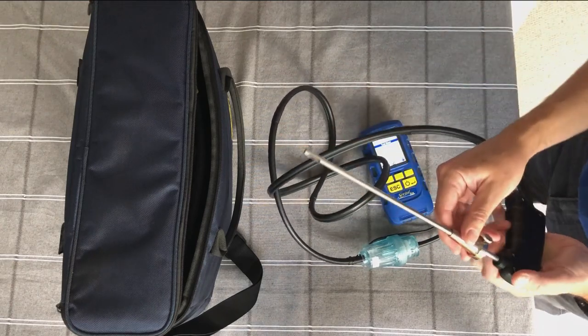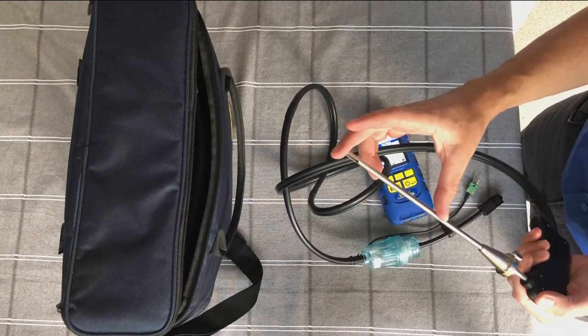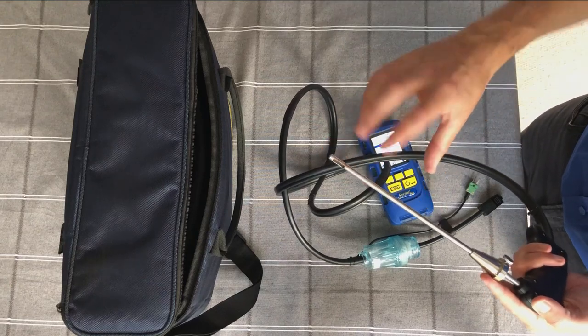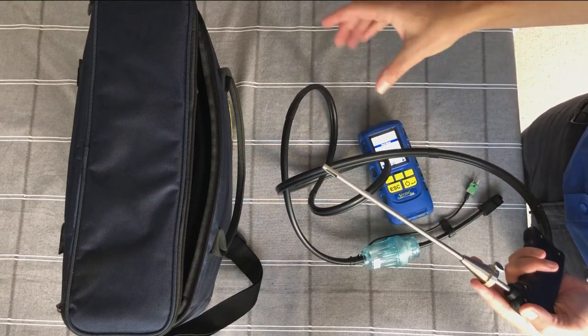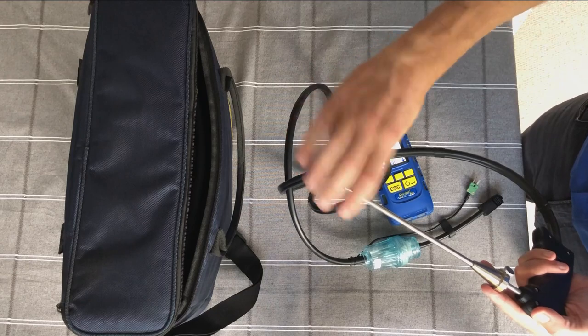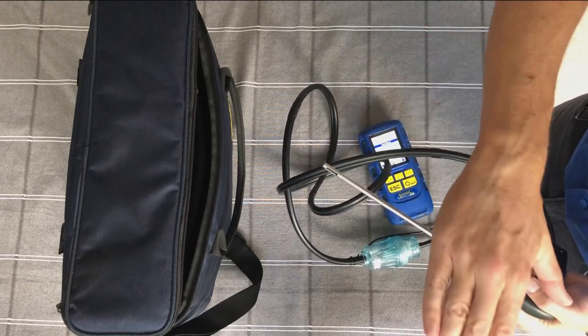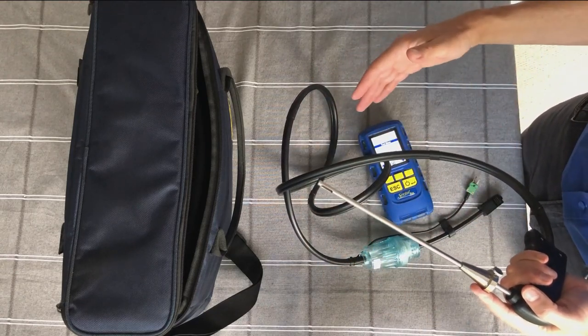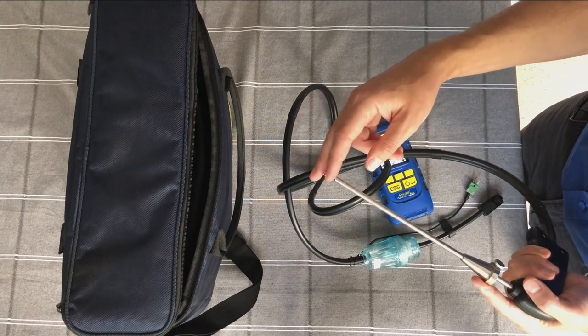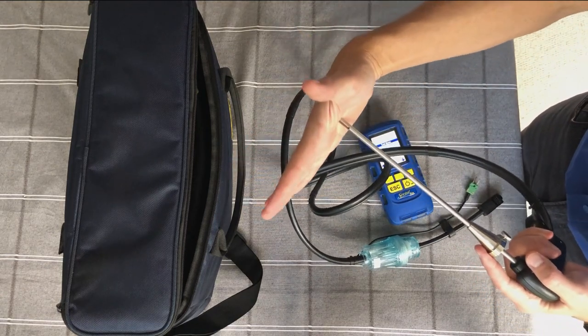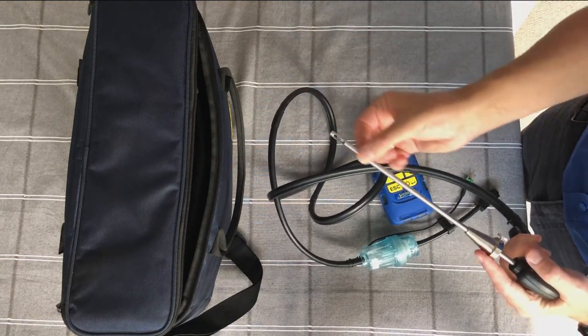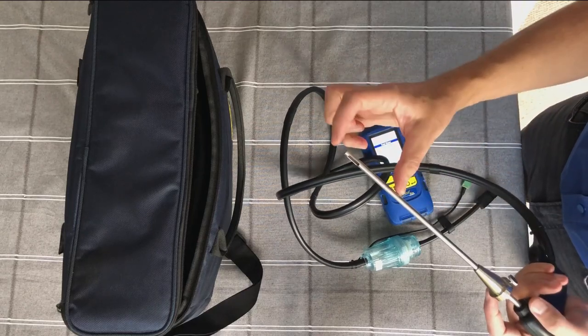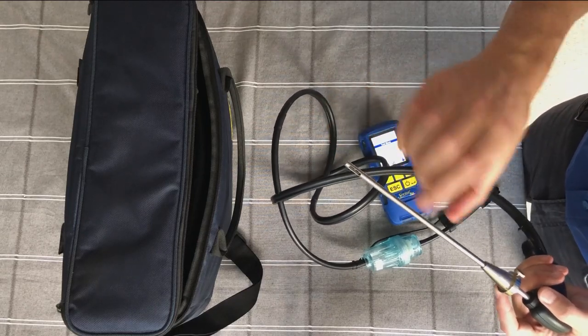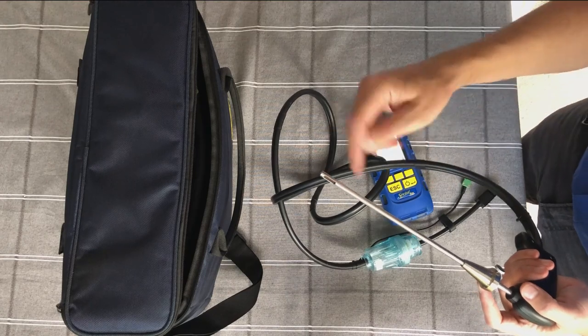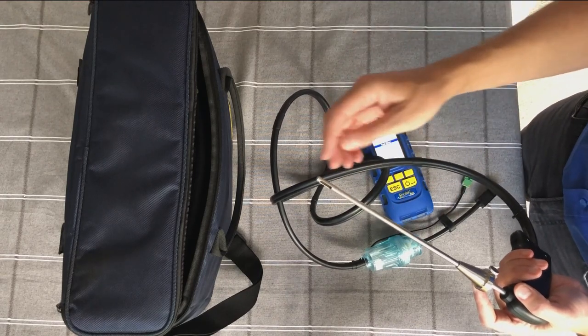Really important when you are inserting this into a flue, think about these concentric flues now. You don't want to be banging it into the inside wall of the flue because it's a condensing flue. There'll be condense running down the inside of that flue. Obviously, if you push that right against that wall, you'll start sucking water into here. What you want to be doing is try and get the tip of the flue probe in the middle of the flue so that you're actually sampling the flue gas.